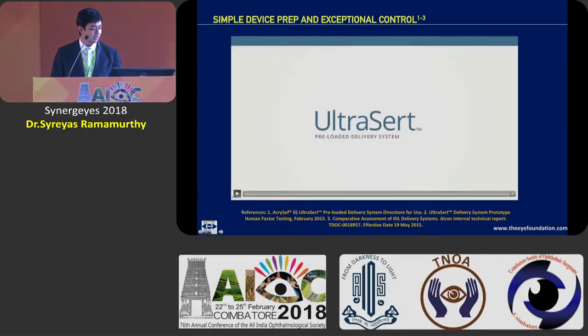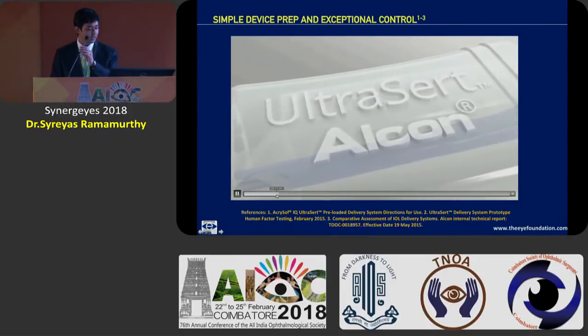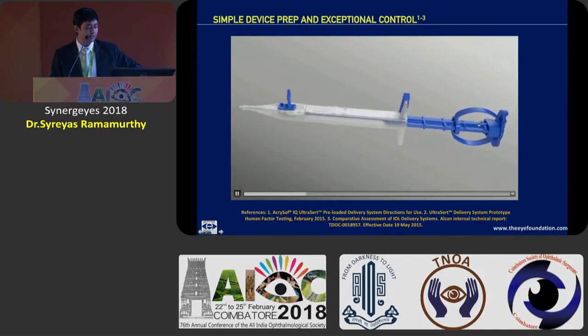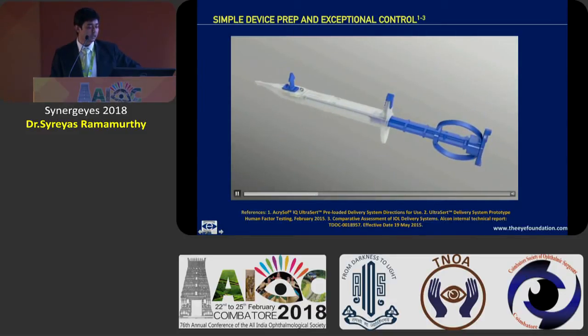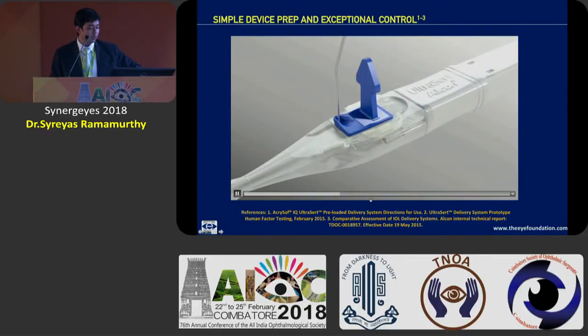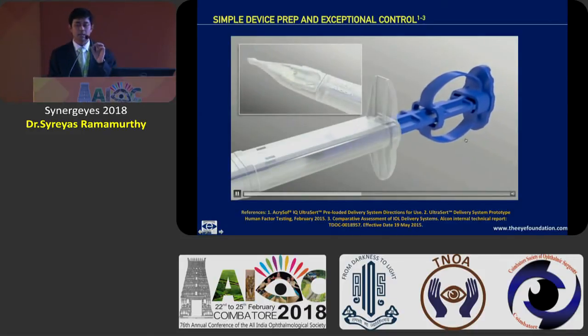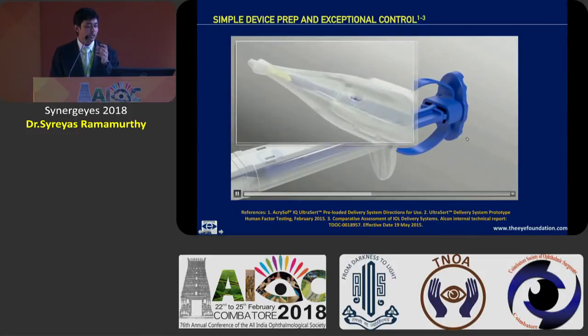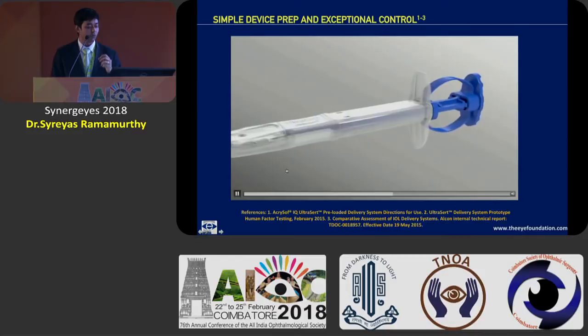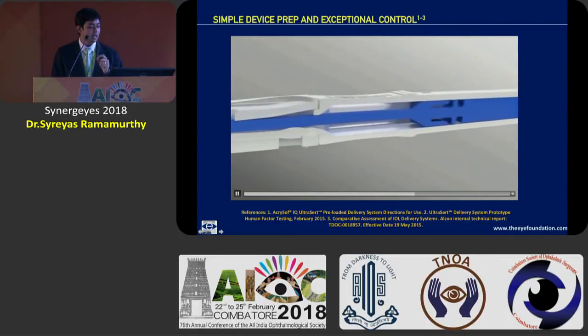Here is a video showing the Ultrasert system in greater detail. It comes in a preloaded system with the nozzle, depth guard, lens stop, plunger lock and tension glide plunger. The company recommends injecting an OVD — preferably Viscoat — into the small cavity, and once the viscoelastic has advanced, you remove the two locks and advance the plunger. Advancing the plunger should be done gradually over about seven seconds, ensuring the lens advances towards the nozzle. Both haptics should be well folded and visible for inspection, and the elastic spring mechanism ensures there is no sudden expulsion of the lens as it is injected into the eye.